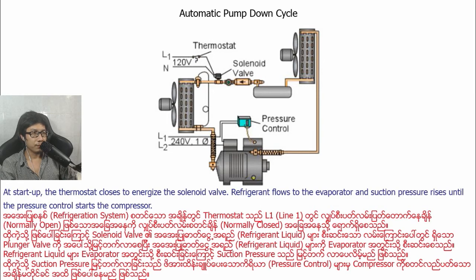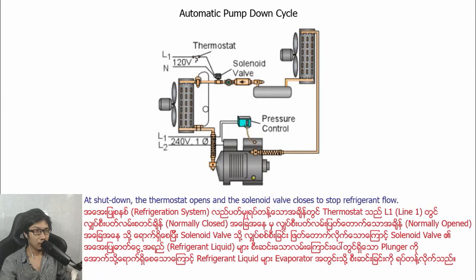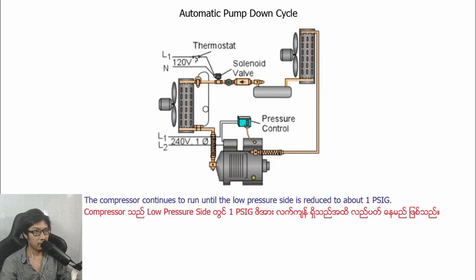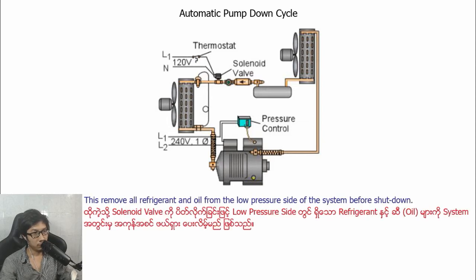At startup, the thermostat closes to energize the solenoid valve. The refrigerant flows to the evaporator and suction pressure rises, and then the pressure control starts the compressor. At shutdown, the thermostat opens and the solenoid valve closes to stop refrigerant flow. The compressor continues to run, and then the low pressure side is reduced to about 1 psig. This removes all refrigerant from the low pressure side of the system before shutdown.